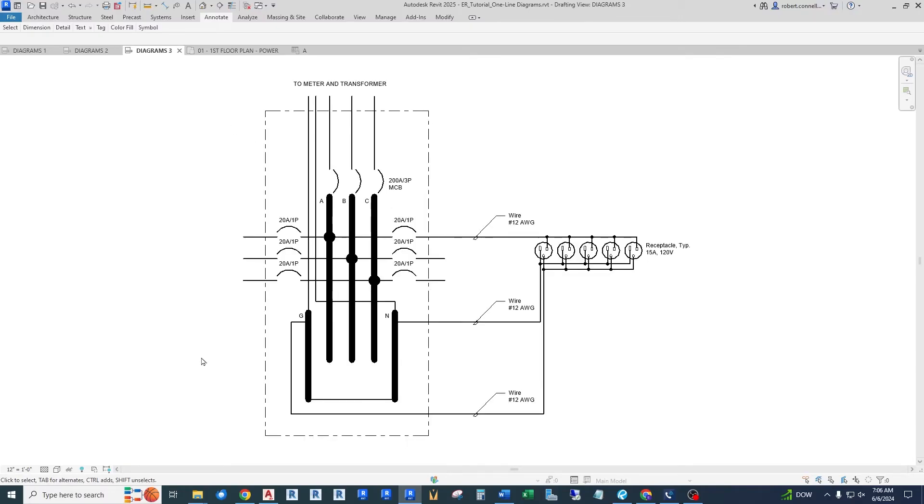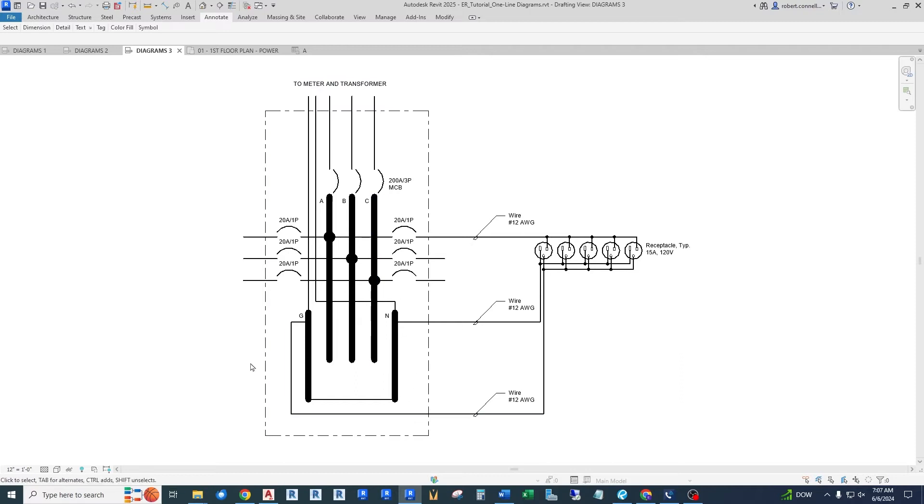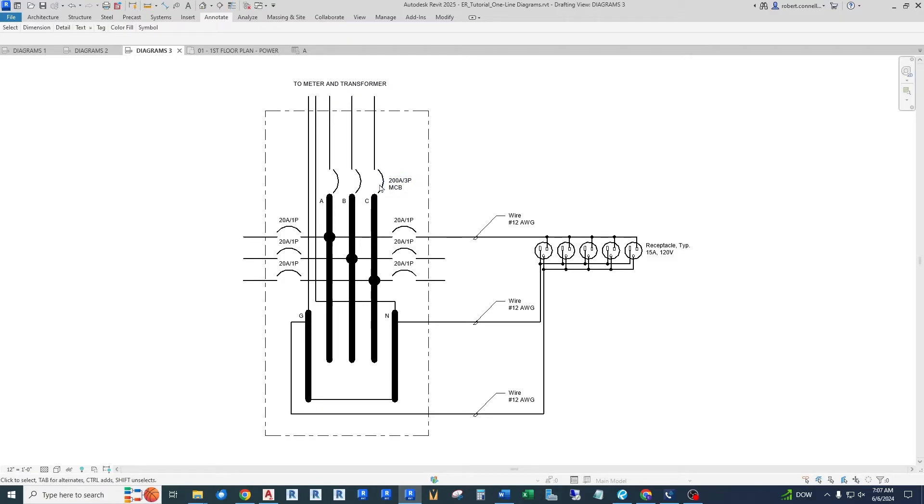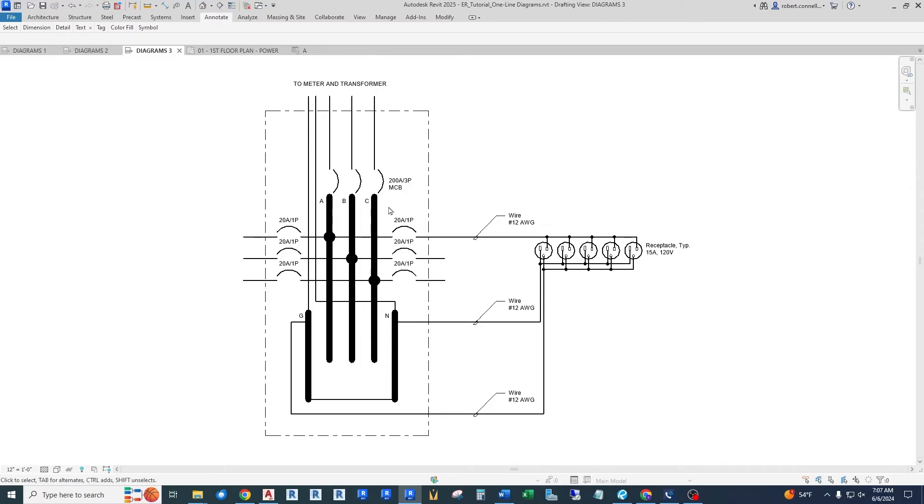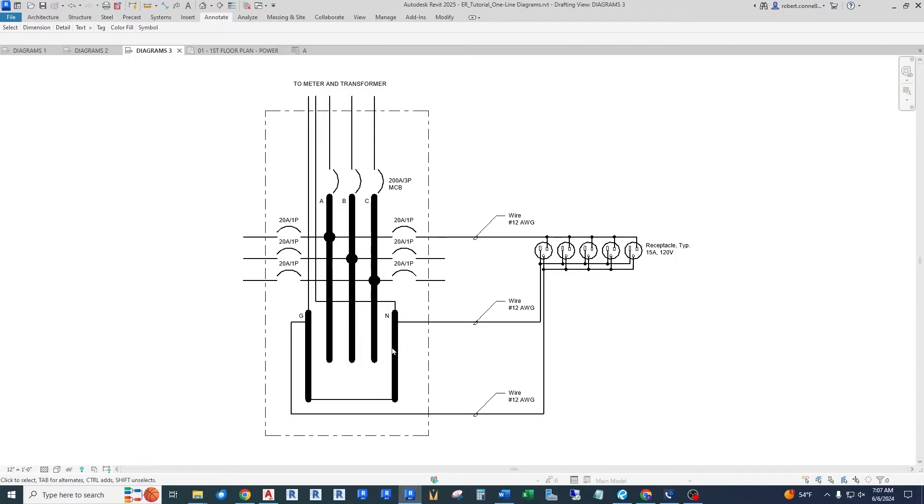So here we're starting to get a little more complicated. But if we break this down, you will see what we have here. This is representing a three-phase panel board in, say, a small commercial building. It's just a 200 amp system. Your house would be similar, but it would only be two phases instead of three. This is a schematic or wire by wire view of this system. And what I've got here is the internals of the panel board with three bus bars, A, B, and C. We have a neutral bus bar and a ground bus bar. They are bonded together because this is the main panel.